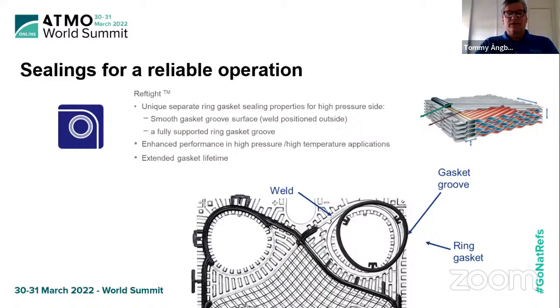But one important thing is that between every cassette on the high pressure side, we have a ring gasket to seal it off. And that is a very critical part, especially when we come to higher temperatures and pressures. That's why we have developed this Reftight with a fully supported groove, and that is smooth. And with gasket material also developed for high temperature. So a very special part of our development, important for reliable operation over time and an extended lifetime.